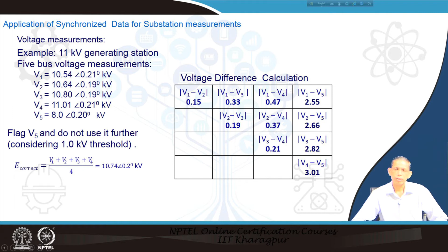Therefore, the corrected value after discarding V 5 is V 1 plus V 2 plus V 3 plus V 4 upon 4, and that gives us 10.74 with angle 0.2 degree. So, this value should be used at the substation level or dispatched to the other centers. This gives us a refinement perspective for the substation voltage and a scope to discard bad voltage measurements. Thereby, we can suspect the associated PT or the device itself, and then we can have the correction for that.